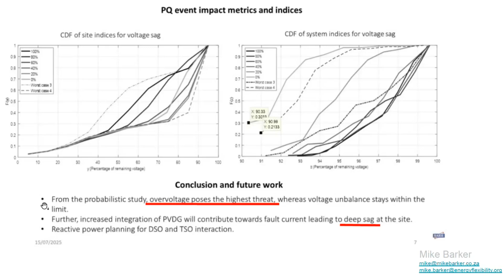So the mandatory issues are protection and tripping. When exactly do you trip your inverter? There's a number of approaches laid out. Voltage ride-through is actually not tripping, but it's at least giving the grid a chance to perhaps recover before you start dumping millions and millions of inverters.